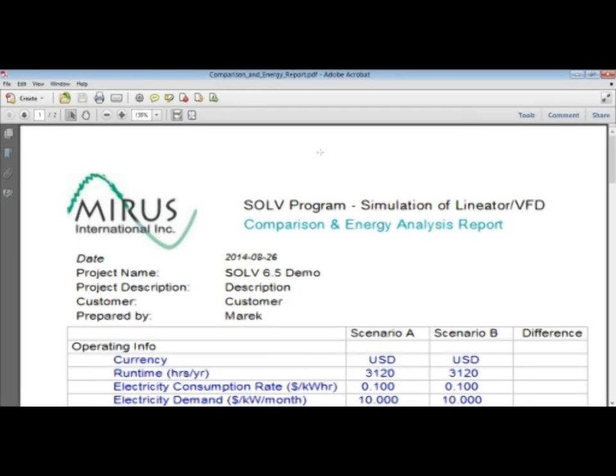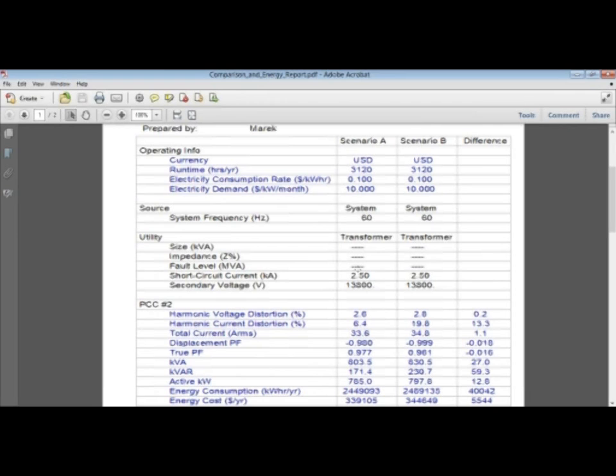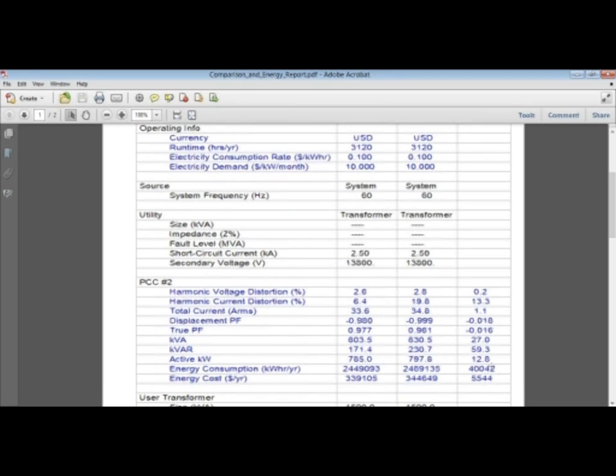I will scale it down a little bit. So looking at the energy consumption and energy costs, we can see that significant annual cost savings can be achieved with the lineator AUHF solution. The difference column shows above $5,500 advantage of energy cost per year. The positive sign in the difference column indicates that scenario B has a higher number, and scenario B was the 18-pulse solution. In this case, obviously, if we set the operating runtime for 24 hours and 365 days in a year, the savings will be even higher. So I'm closing this report right now.